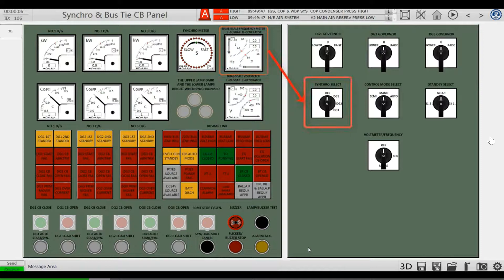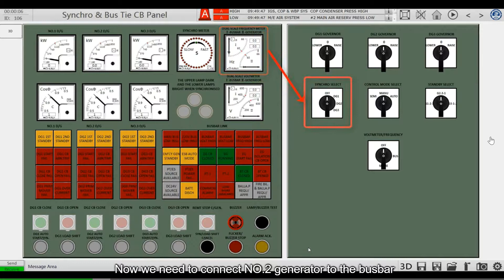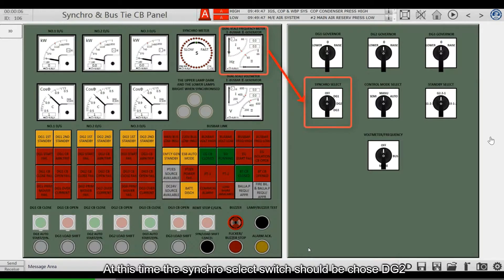If number 1 generator is already in the grid and we need to connect number 2 generator to the bus bar, at this time the synchro select switch should be set to DG2.